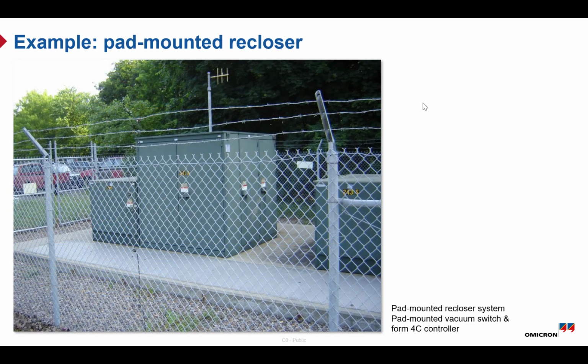The third example is the pad-mounted recloser, which is a metal-enclosed recloser and looks like the ring main units in use. In this case, the same recloser components are used, but instead of being installed on a pole, everything is mounted at ground level on a pad. This setup is commonly used in the distribution system, especially where a full substation is not required.